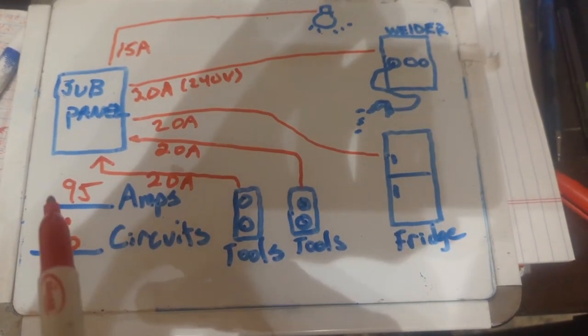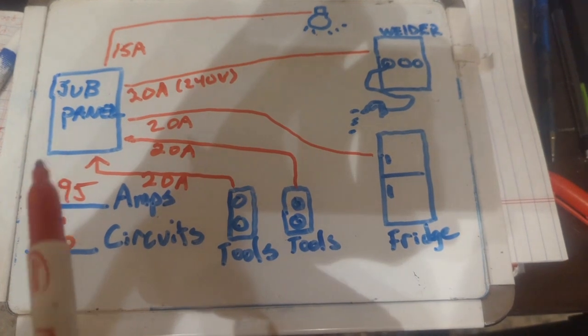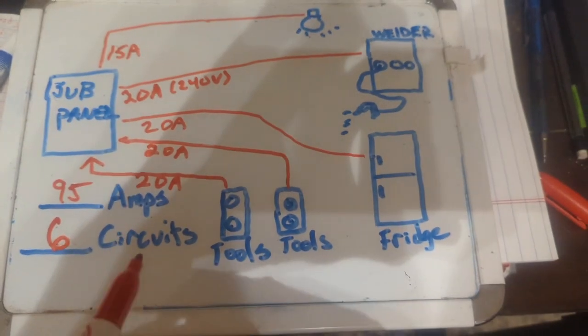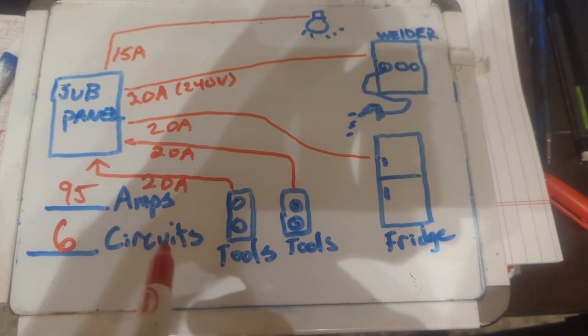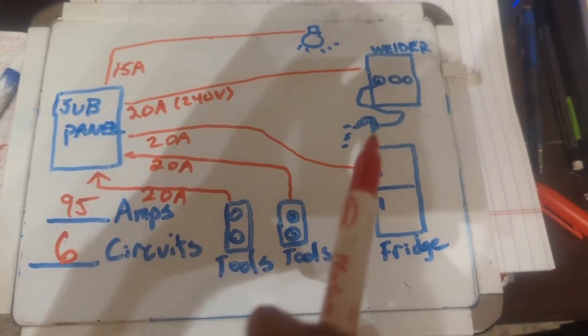So in this situation here, I'm going to say I'm going to go with a hundred amp box and hope that I don't have to add anymore and I'm going to need six circuits in there. So that's what I'm going to be looking at for this. So that's how you determine the box.